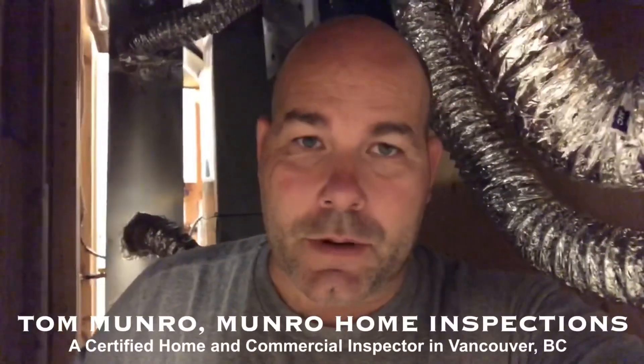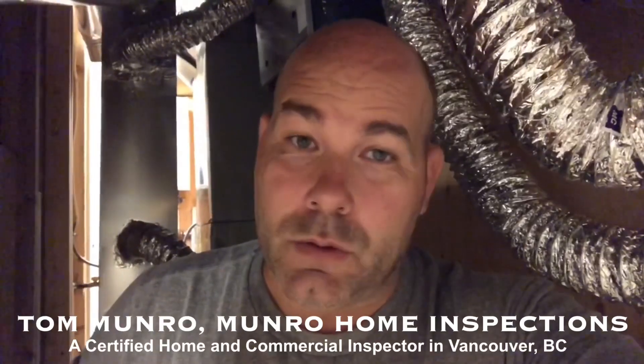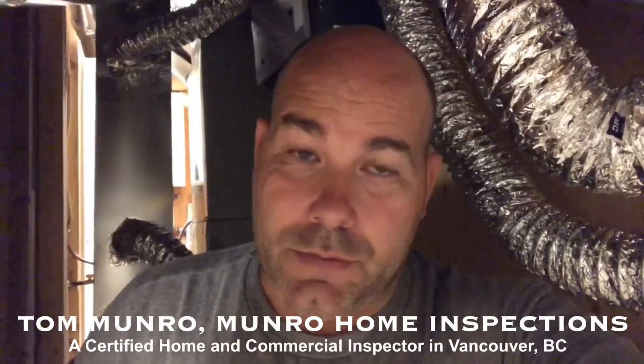Hi there, I'm Tom Munro of Munro Home Inspections. I'm on an inspection today of a 5,200 square foot home in North Vancouver, British Columbia. This home has its final occupancy and final inspections, but I've come across an HRV system that is clearly undersized for this home. I'm again surprised this passed its final inspection, but I've been told that district inspectors don't inspect HRV systems — so maybe that's the problem. Let me show you why it's so important to have your own independent inspector so this doesn't happen to you.